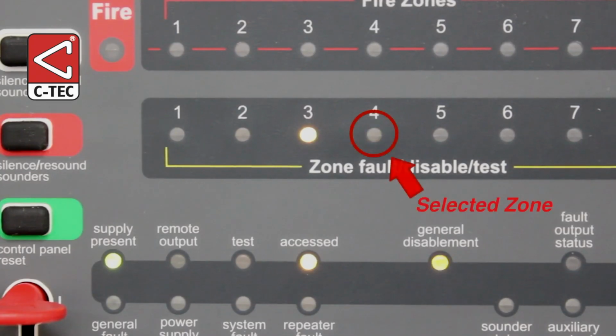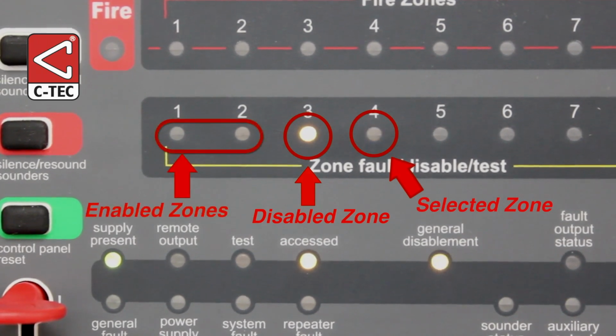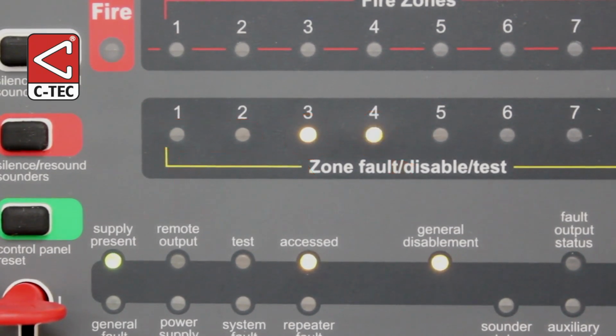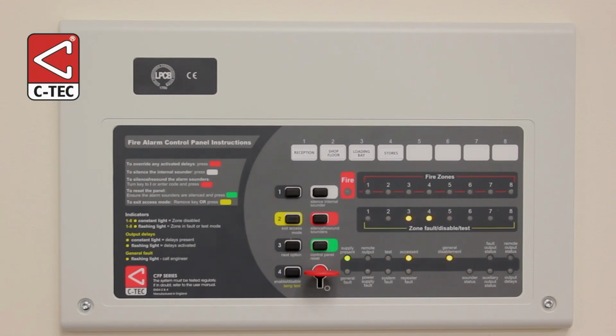The fault light for Zone 4 is flashing. Meanwhile, the fault light for Zone 3 is lit steady to confirm it's disabled, whilst Zones 1 and 2 lights are off to confirm they are enabled. The selection process can also be used to enable and disable the panel's fault output, remote output, all of its alarm devices, its auxiliary output, or any delays programmed into the panel.